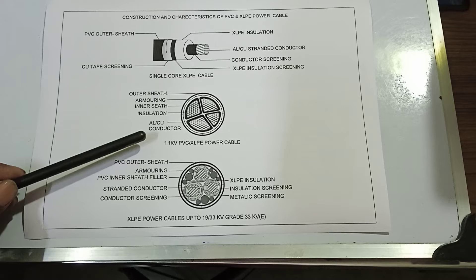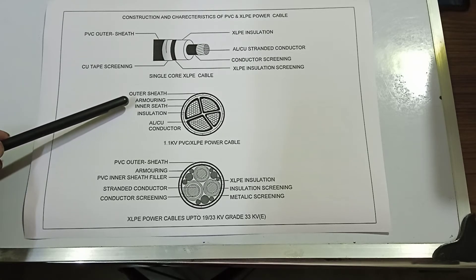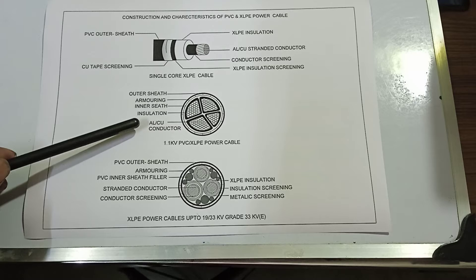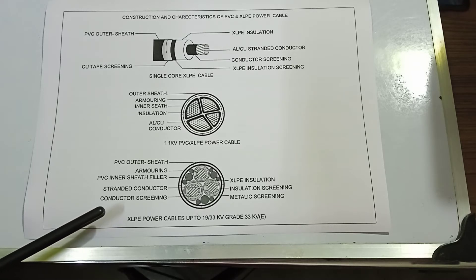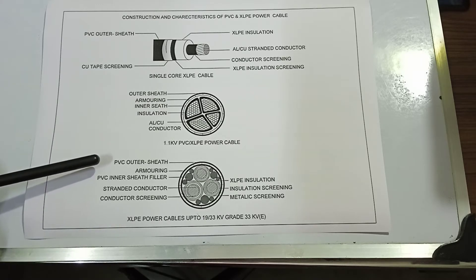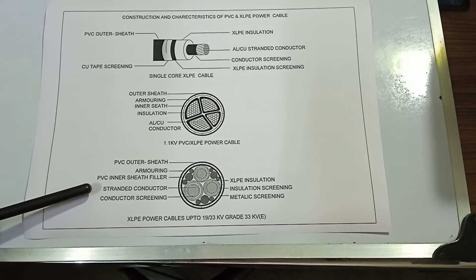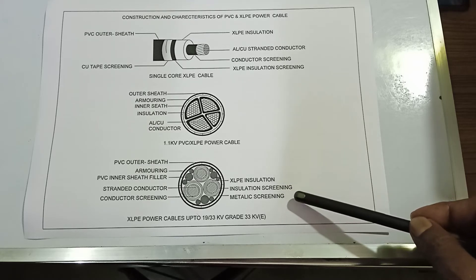Here is a 1.1 kV PVC or XLPE cable cross-sectional view. There is an outer sheath, next is armoring, next is inner sheath, next is insulation, and next is an aluminium or copper conductor. Here is XLPE power cables up to 19/33 kV grade — 33 kV (E) grade — with PVC outer sheath, armoring, PVC inner sheath, filler, stranded conductor, conductor screening, XLPE insulation, insulation screening, and metallic screening.